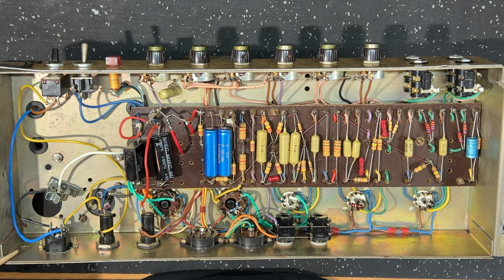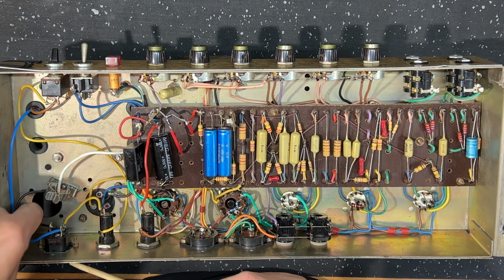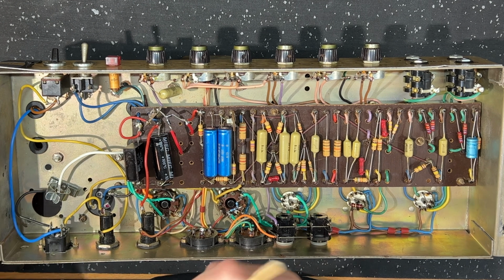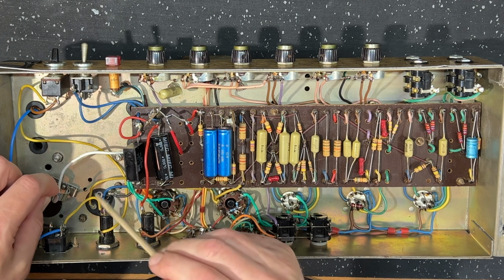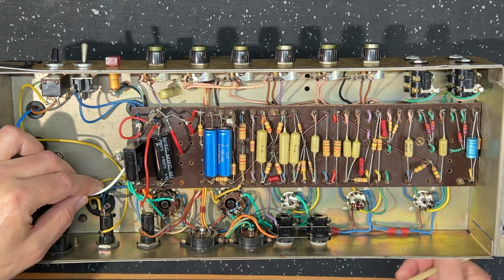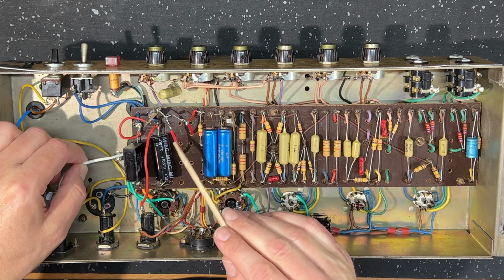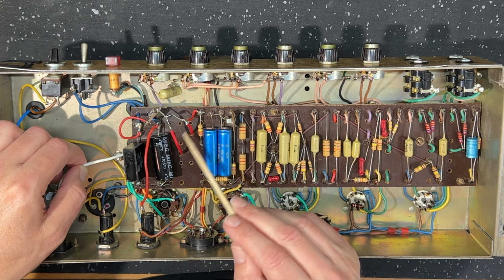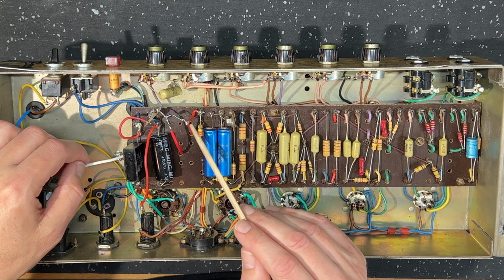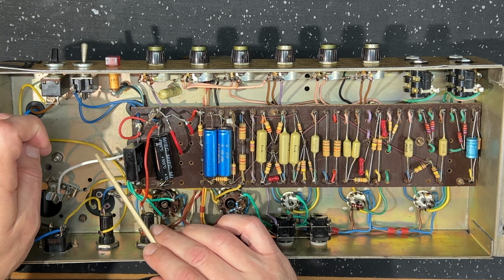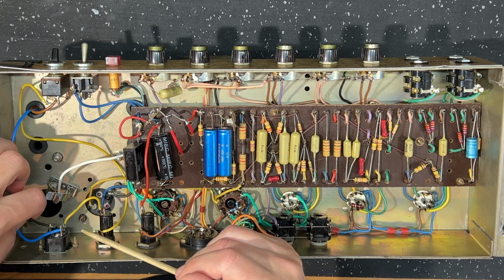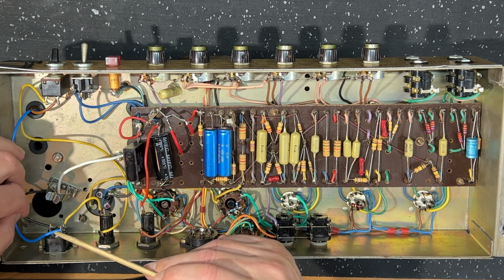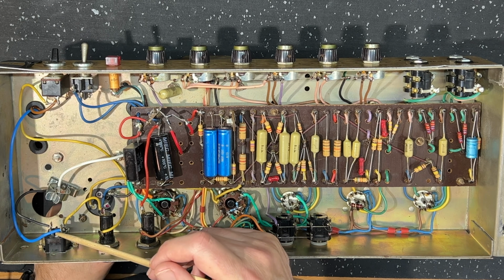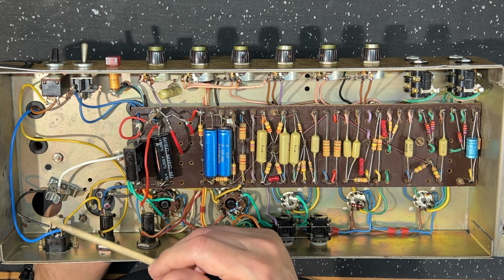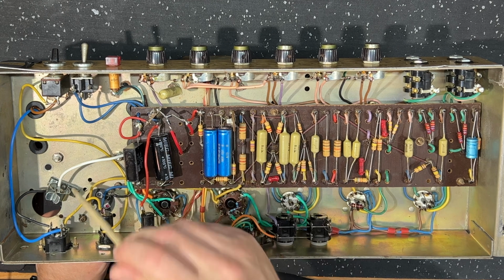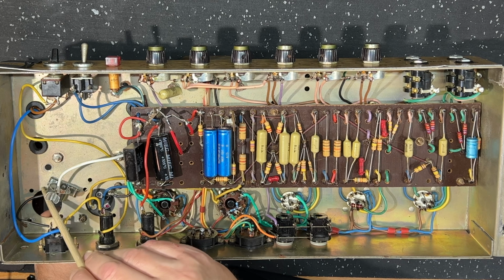The other thing I've noticed, which I don't like, is that the ground for the IEC is a shared ground with this white wire here, which is the center tap for these secondaries. In a 2-phase rectifier setup, your high voltage secondaries will have a grounded center, but your ground for your IEC connector, your main earth, should always be separate, run to its own ground lug, away from where it's shared with anything else. That's just common practice for safety. That's not good.